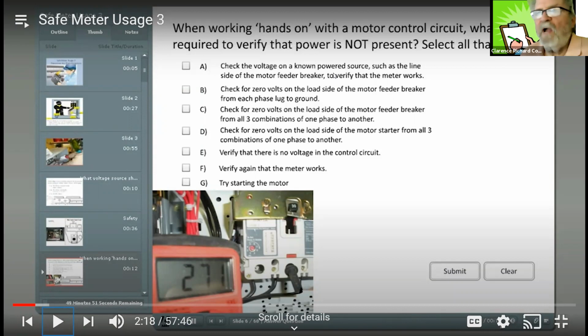What I would say is trying to start the motor. If you remember when we were going into safety, I believe, did you take the safety day, Justin? I did, yep. Okay. Remember there that we had steps for lockout tagout, and one of those was to verify, after you've done your lockout tagout, try to start it up. If it starts up, then surprise, surprise. This is one of those things OSHA likes you to do. So I would say try starting the motor, and that's kind of a way to verify. So I don't think that's entirely out of the question.